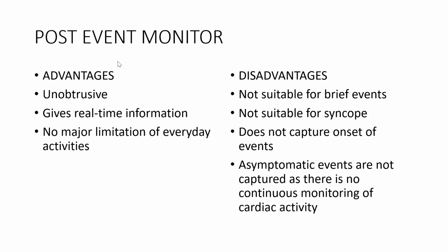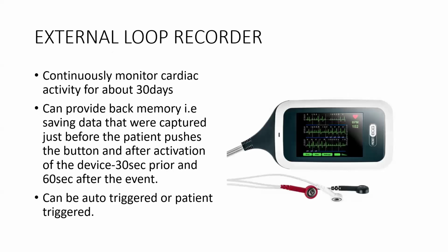Okay, so that was for the post-event monitor. The major drawback is that it does not continuously monitor cardiac activity. It needs to be activated during the period of the event. So it's not suitable for patients that have syncope or patients that have brief events.